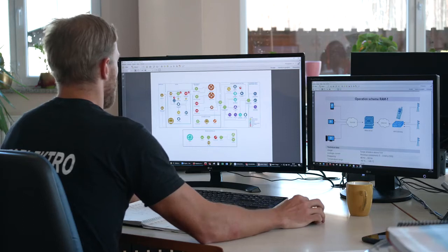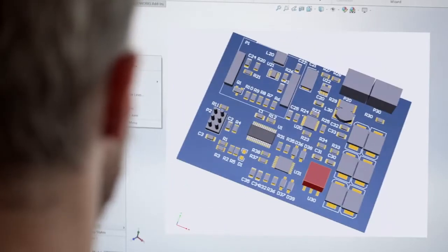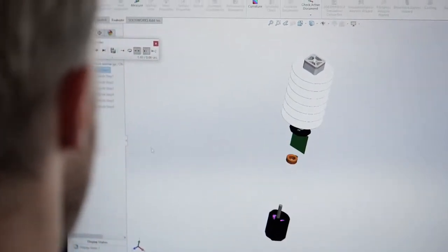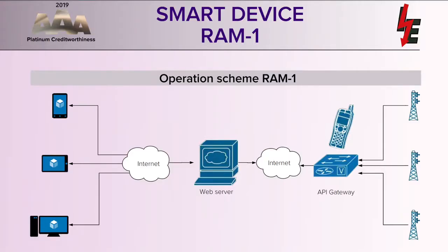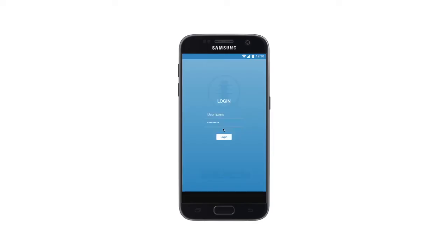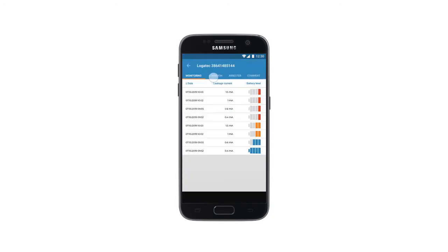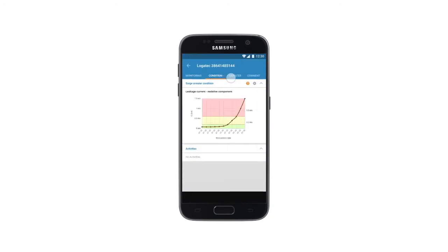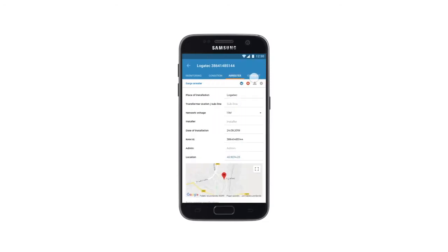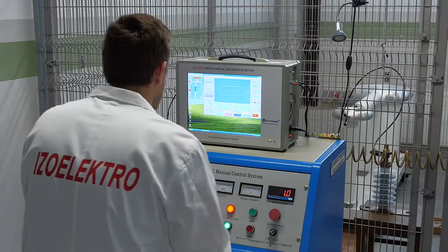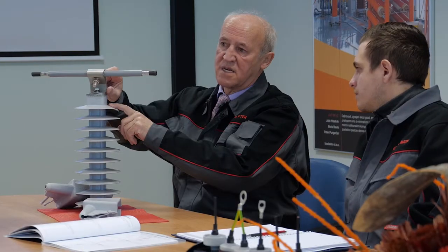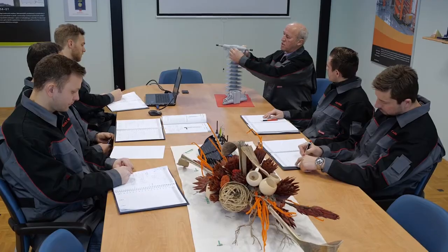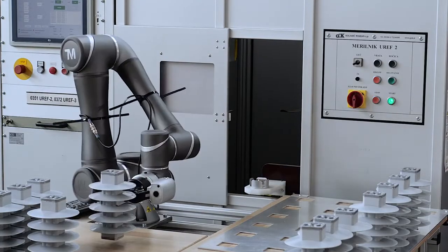At the request of our end users, we have developed and produced a new, innovative condition monitoring system for surge arresters, RAM1. It enables the user to remotely monitor the condition of the surge arrestor from 3 kilovolts on. RAM1 sends the following information to the user: resistive component of the leakage current according to the standard, ambient temperature, number of lightning strikes, location, and position of the installed RAM. We consider the fact that our surge arresters are present in all of the most demanding markets to be a very good indicator of the quality we have to offer.